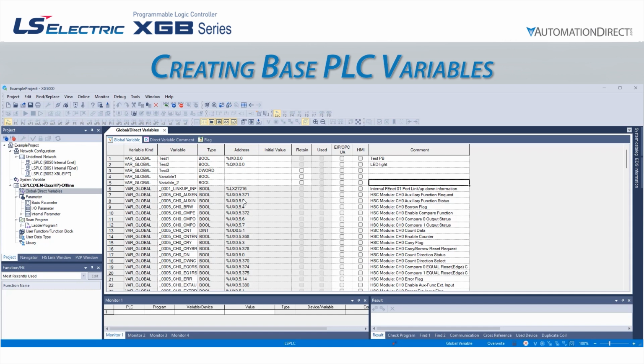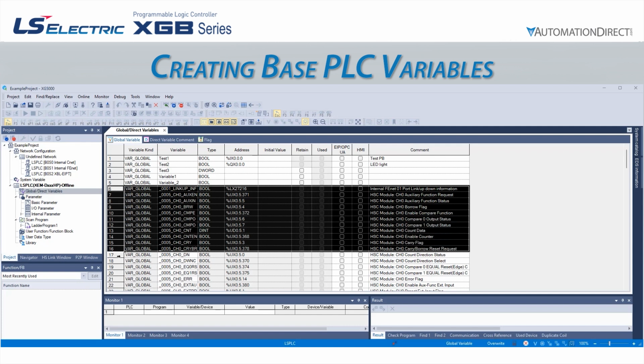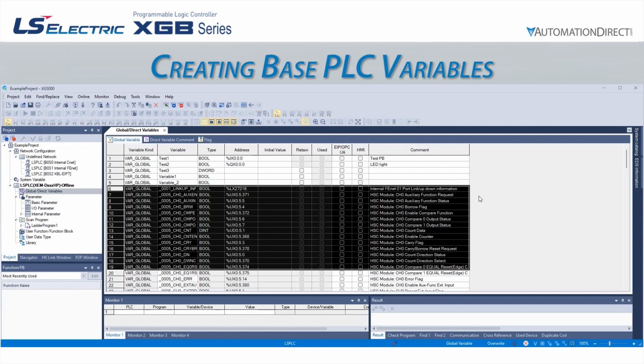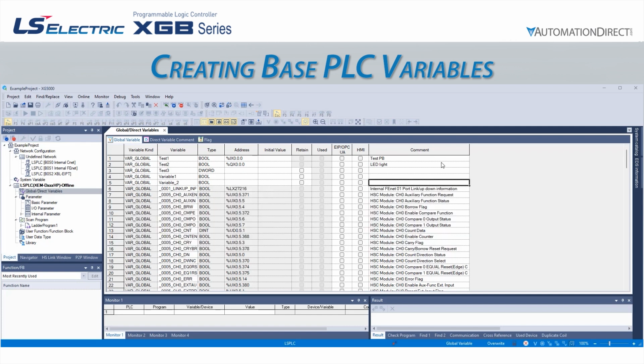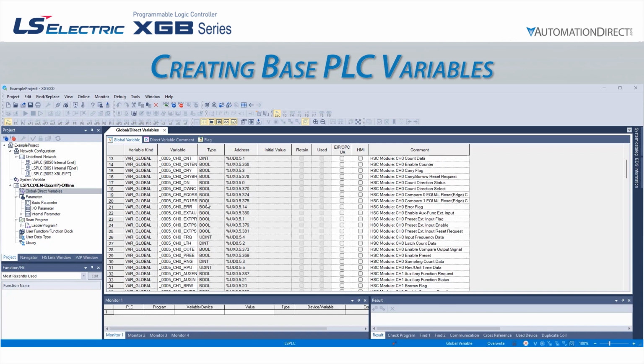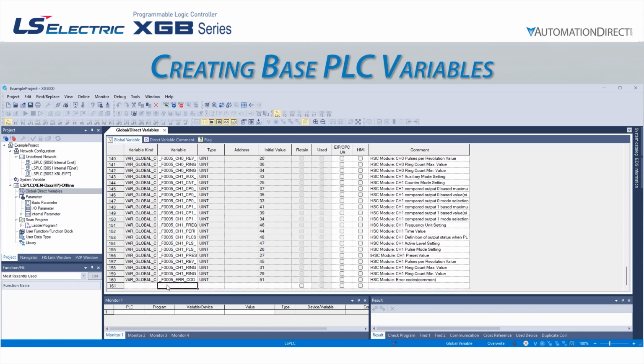On the Global Variable tab, we see all currently created global variables. This will include any automatically generated variables based on our expansion I/O modules. To create a new variable, scroll all the way to the bottom of the list and start typing a new variable name. Once we finish the variable name, we will press Enter and the variable will be created in the project. It will automatically assign the variable kind and the data type. Both can be edited by using the drop-down for each column.